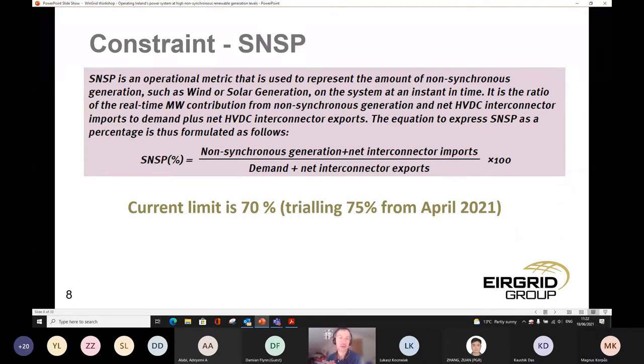One of the key constraints we have is a metric called the System Non-Synchronous Penetration Limit, SNSP, defined by this equation. It's essentially the amount of non-synchronous generation plus our net interconnector imports, remembering these are HVDC imports, not synchronous interconnections, over our demand and net exports. This is a metric we developed just over 10 years ago to help us manage and capture a number of issues with the operation of power systems as we introduce more non-synchronous generation.